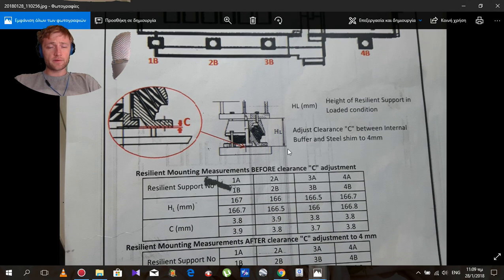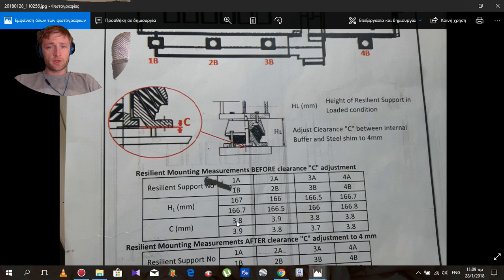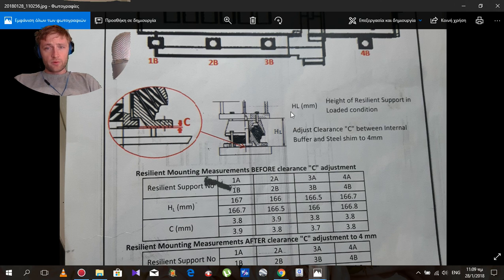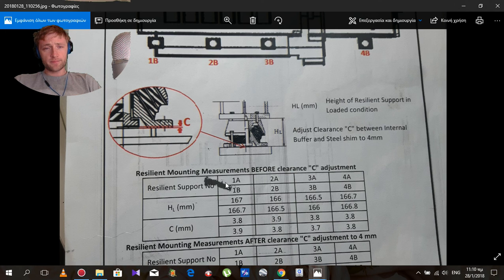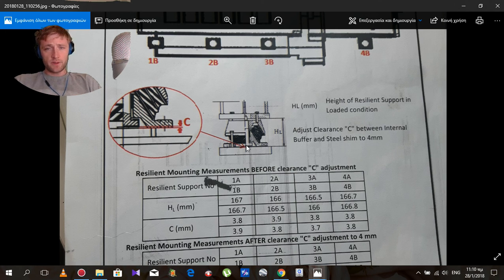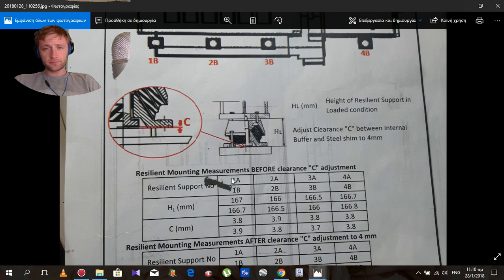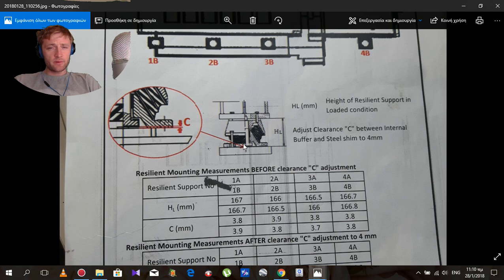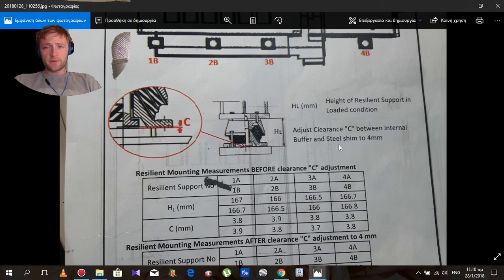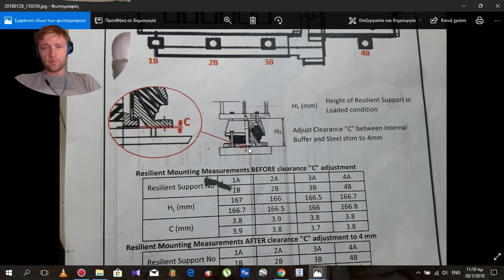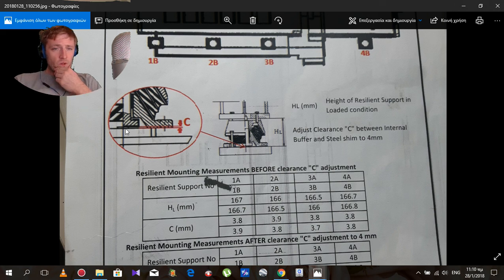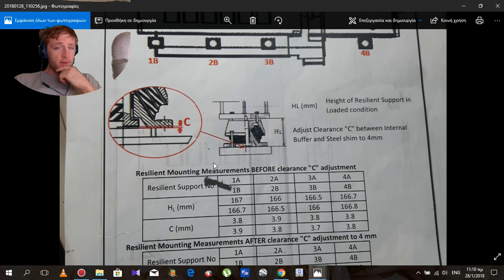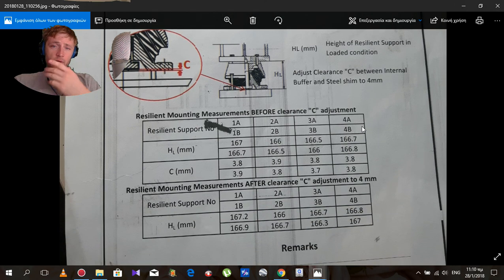This is how it looks in the sketch, this resilient. What we measure is this HL from here to here in millimeters. And also the C, which is inside here, and we need to adjust this clearance C in the middle between internal buffer and steel shim to 4mm. Here down is what we have.